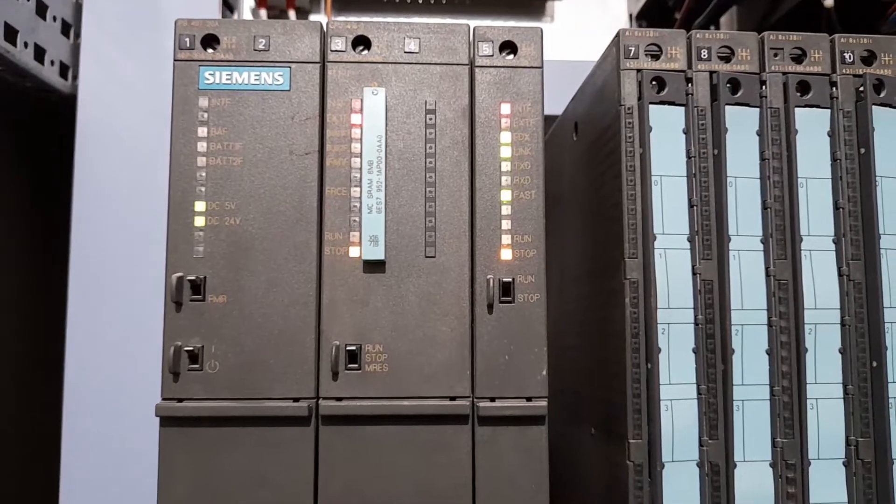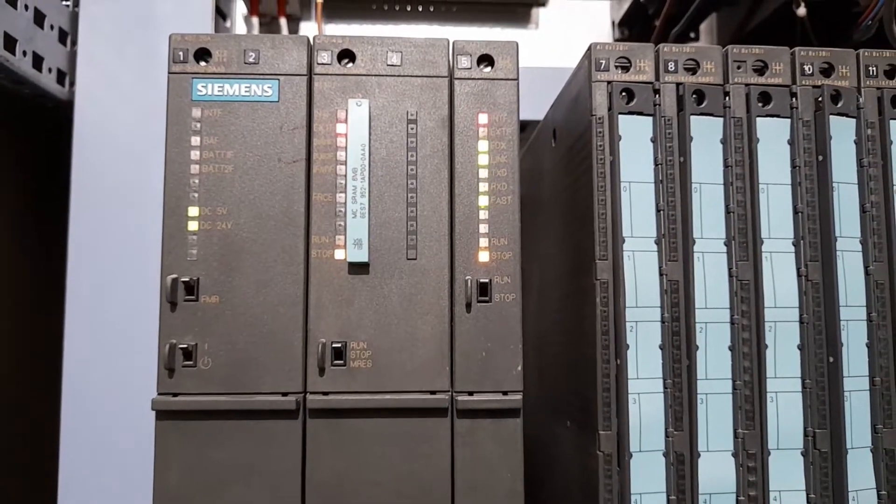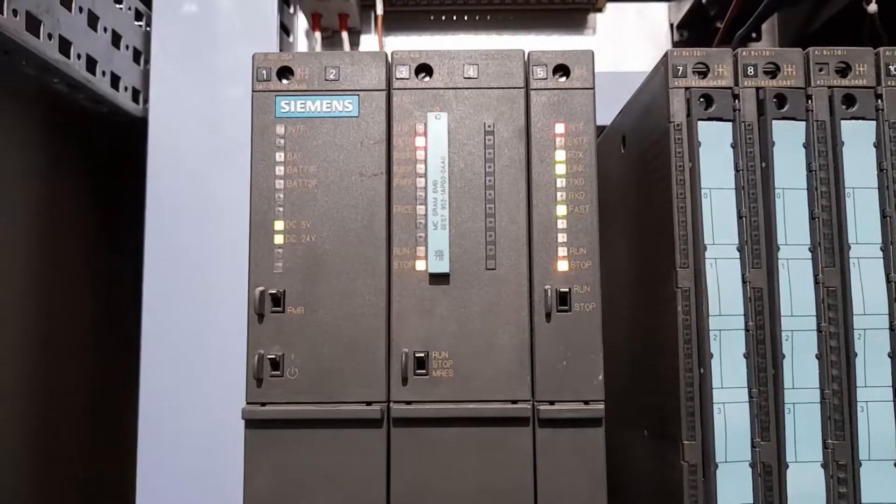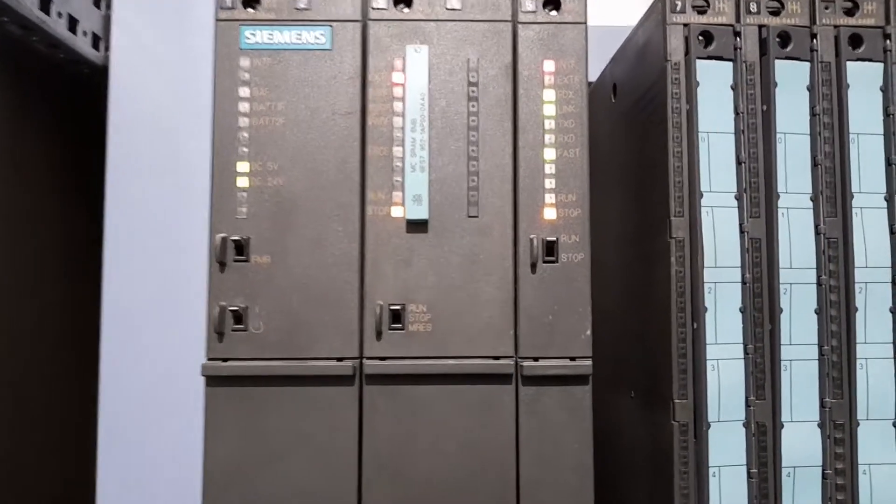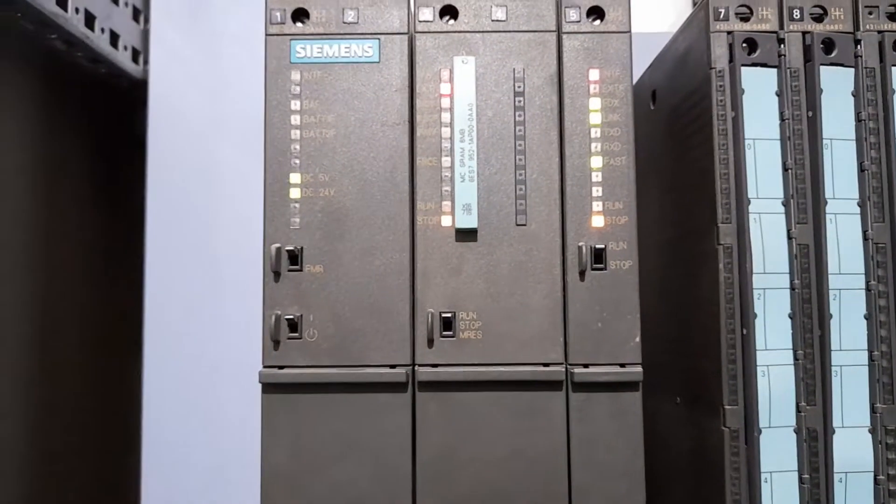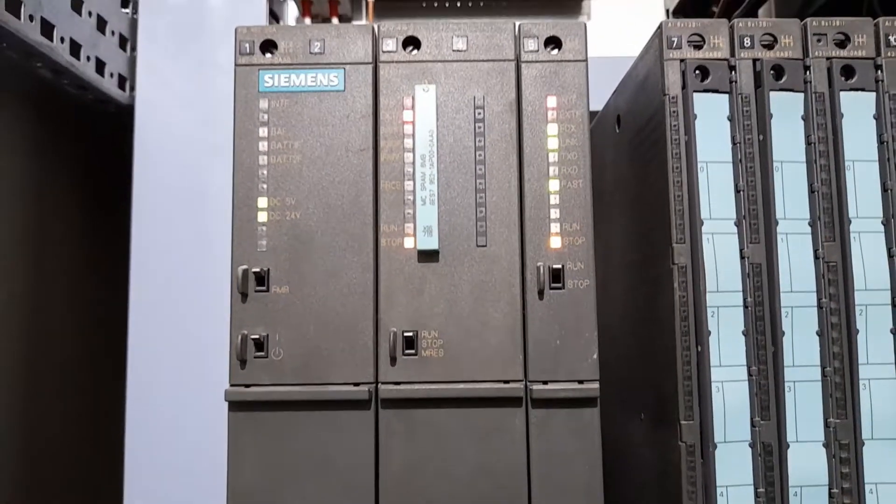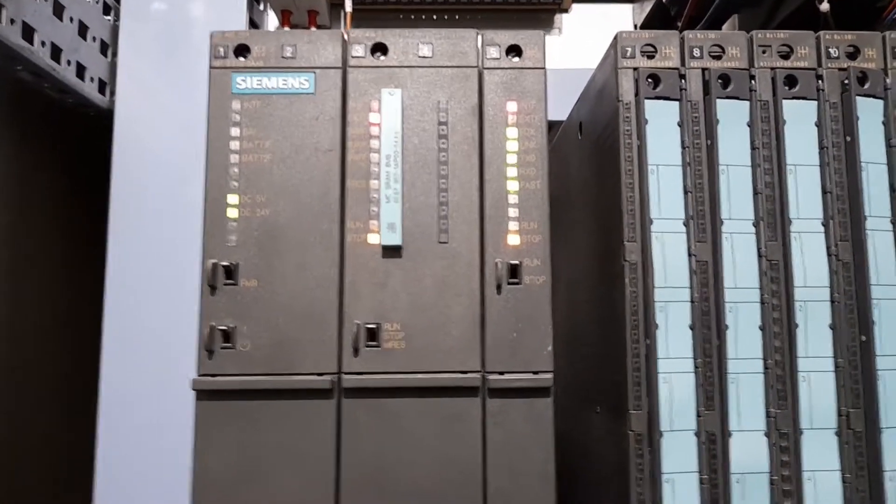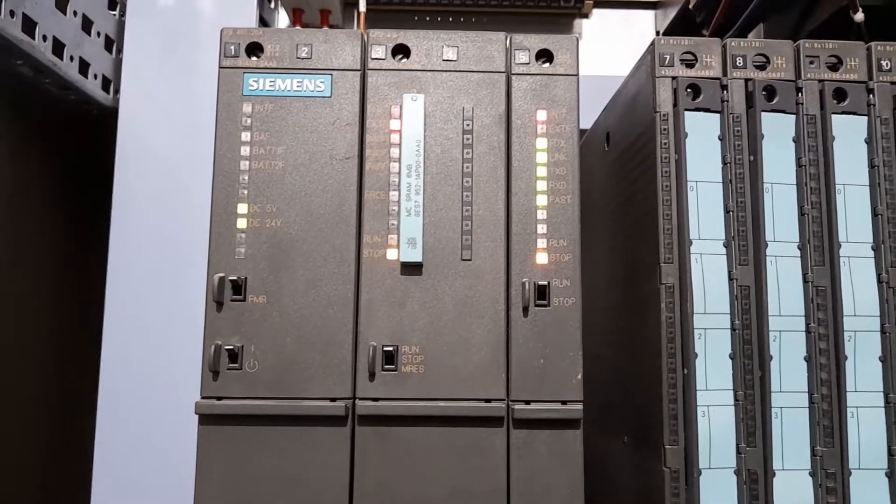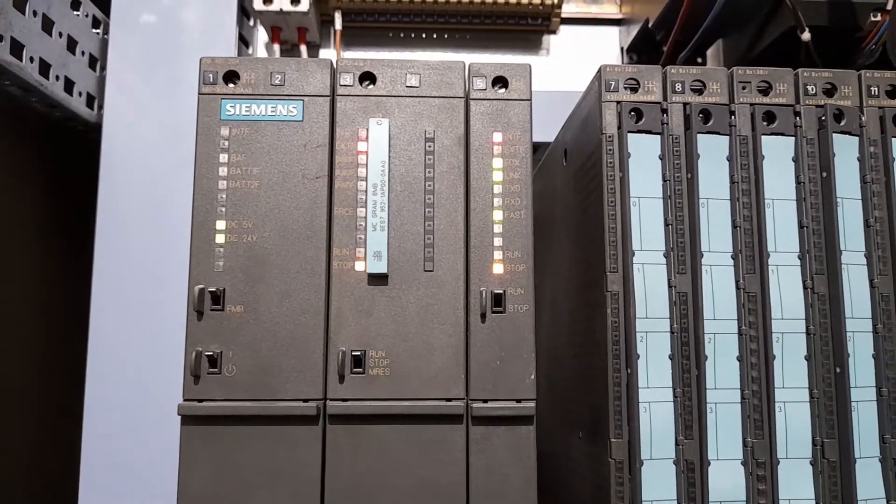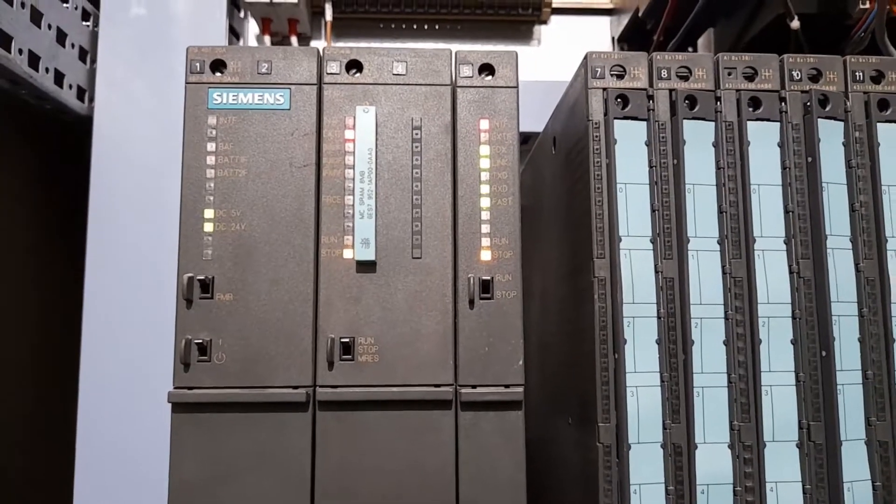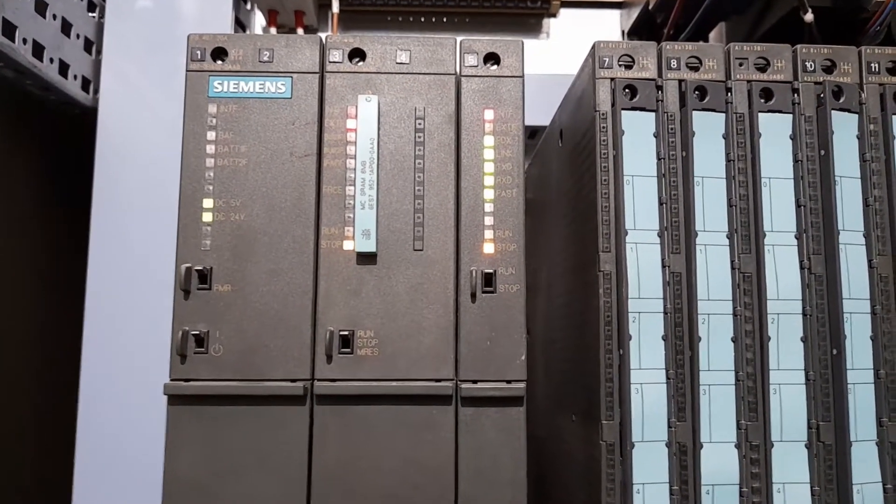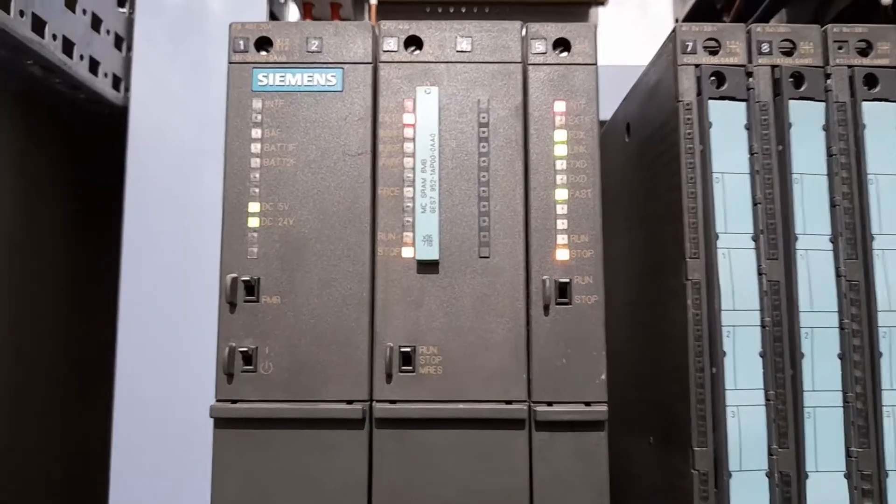The solution to this problem is we have to re-download the program from the engineering station to this CPU memory card. I have to re-download the entire configuration, that is the hardware configuration, that is the logic and the network configuration. All these three configurations need to be downloaded into this CPU.